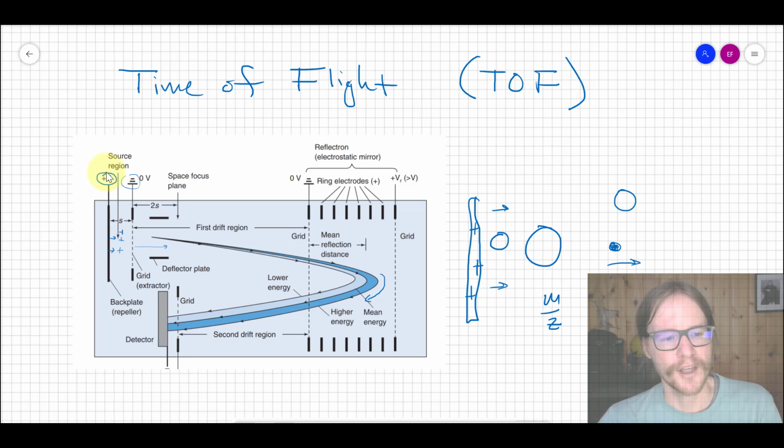This is like an electrostatic monochromator for mass, the way I think about it, because it takes all these ions that start at the same point in time, and they drift apart in the drift region based on mass to charge. Then when they're acted on by the differential voltages across these ring electrodes, they'll penetrate further and further into this series of ring electrodes, and then as they swing back around, they hit different regions of this detector here, or we have a grid here that can allow only ions of certain mass to charge ranges to pass through at any given moment in time.